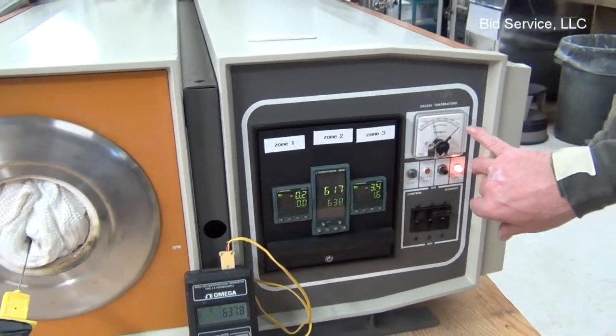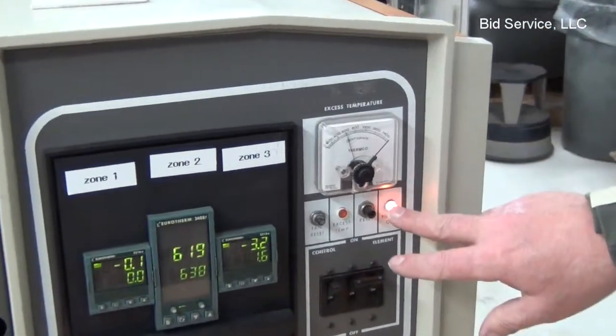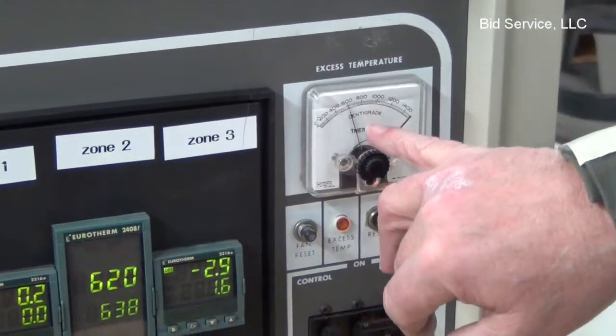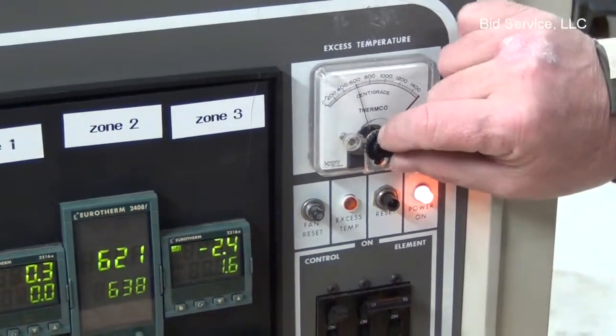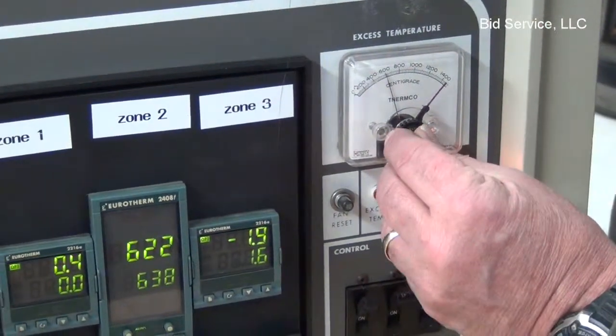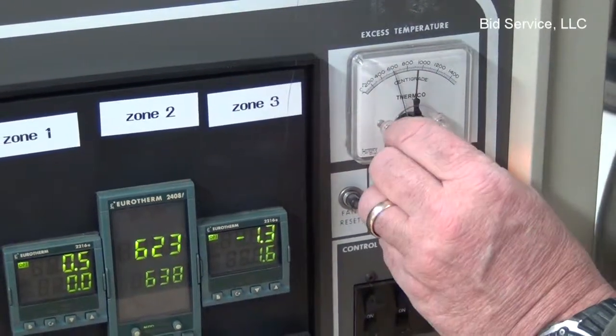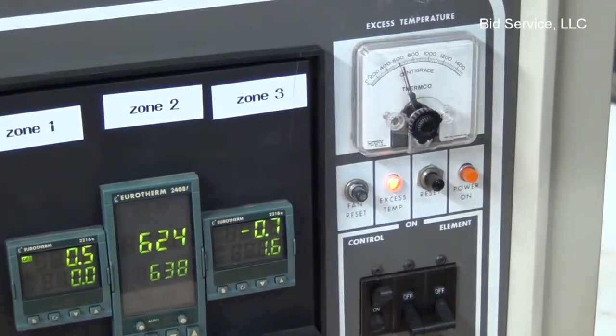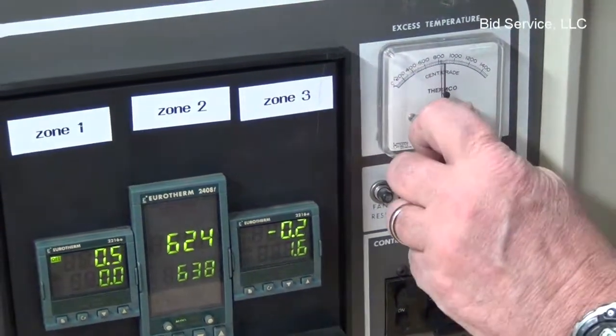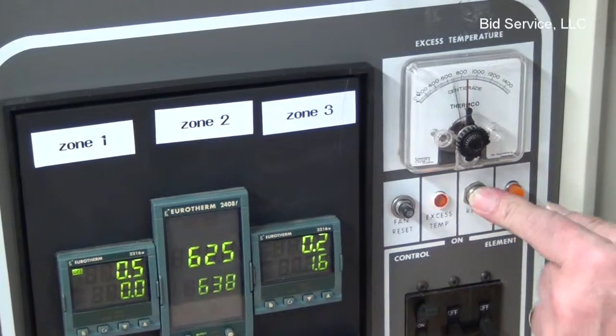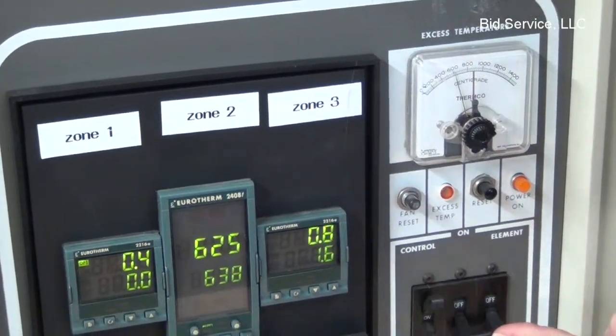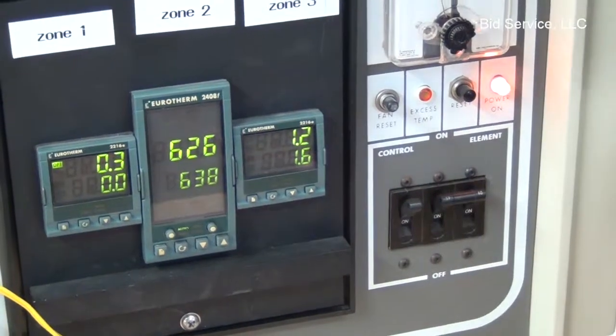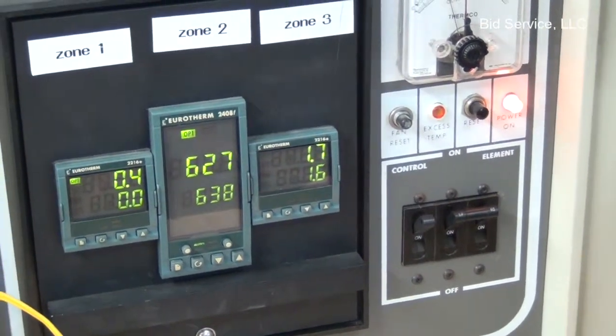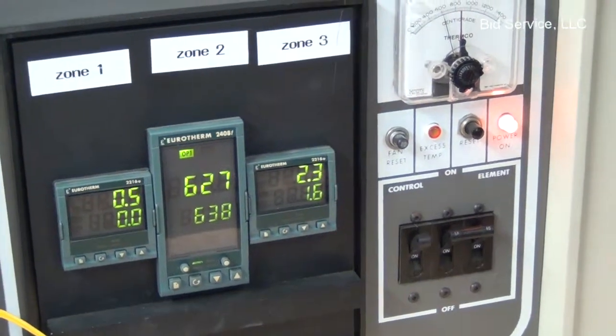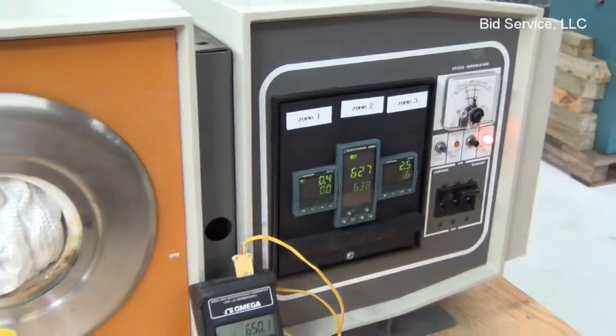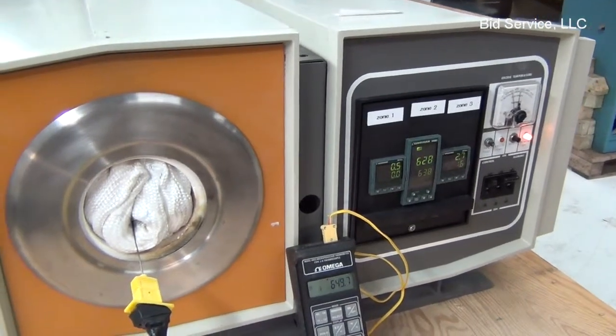Up top here you have your excess temperature gauge and overprotection switches. As you can see, it's reading around 600 right now. If I go down, it's going to trip. So I'm going to show you how that happens. You set this a little bit higher than what you normally would run. You can see it alarms. At that point, you have to set it back up. Hit the reset button, and you'll notice that the circuit breaker tripped. At this point, you can turn it back on, and it'll resume from where it left off at that temperature, depending on how long it alarmed for. So that's it. That's working fine.